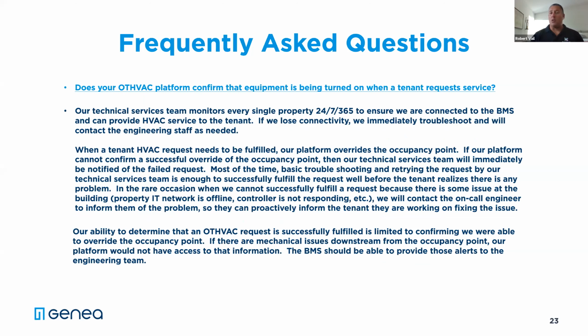Does our platform confirm that equipment is being turned on when a tenant requests service? What we confirm is that a point goes from off to on. So we know in the automation system that a request is made and a point was turned on, meaning a command was issued. Downstream, though, we do not know if a fan physically turns on. A lot of times we'll get calls from a tenant saying, I put in a request and I don't feel anything happening in the building, it probably didn't work. Our first step is we have read-only access to the front end of the BMS. We look to see if the command is good. If it wasn't good, we reissue the command and check if the point was turned on. If it was, a lot of times we'll tell tenants, hey, it's a big building, it takes a little while to get comfortable - give us a call in about 5 minutes if you still don't hear anything.